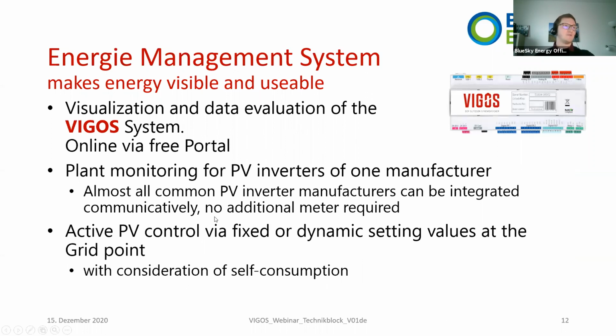And then we have an energy management system, a Vigos EMS, which is doing the visualization and data evaluation of the system. It's also available online. It's a free portal. It also does plant monitoring of PV inverters of one manufacturer. You can choose out of many different manufacturers, but it's only capable of doing one manufacturer at a time. So if you have different inverter brands, you maybe have to add an energy meter to also be able to visualize the power inside the EMS. It's not needed for the function of the whole system, but it's just better to have full data mining available, more or less.